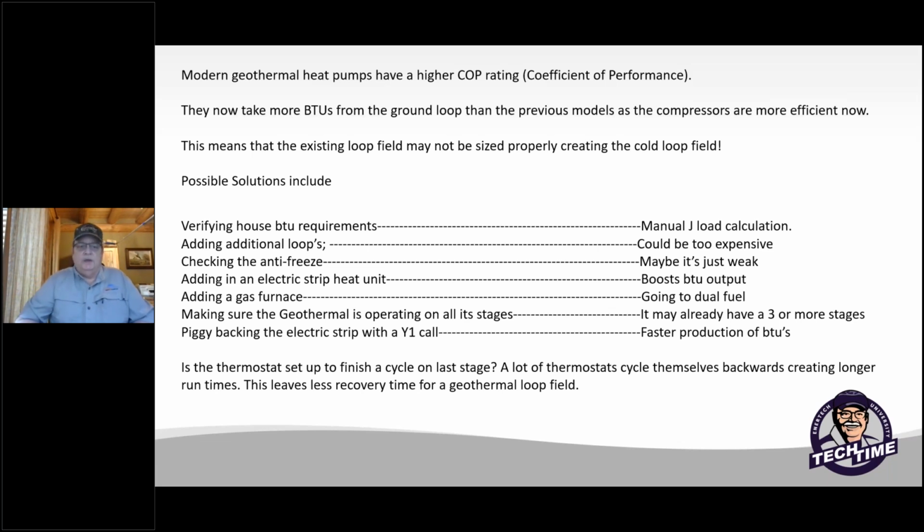One of the other big things we saw a lot this year in tech services was antifreeze protection. We found that this really showed up this year if you had weak antifreeze because of the freezing or slushing up of the units and flow issues, sensor warnings, etc. So again, it's imperative, even if you're doing a retrofit or replacement, what is the antifreeze protection rating? Do you know what antifreeze is in there? Sometimes that's not documented either, and it's kind of hard to know.